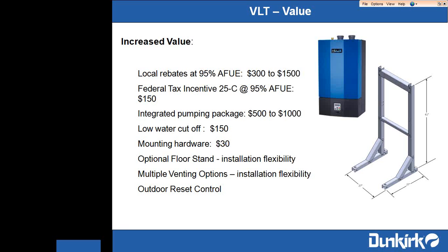Or most recently, we've had the boiler approved so that we can use indoor air for combustion. So again, in areas where there's townhouses, row houses, where an end unit is not feasible, the hardest thing for any type of sealed combustion boiler is how do we vent it? We can't go out the front, we can't go out the back. We certainly can't just bring the vent pipe up three floors through the roof. So now, with the boiler approved for polypropylene venting material as well, that product comes in a rigid pipe or in a flexible coil. With the boiler approved to use indoor air for combustion, the contractor can now take flexible polypro and put it down the chimney and use the existing chimney as a chase, and now they can actually install and vent a Helix boiler in applications where they never could before. Additionally, outdoor reset control comes with every unit as well.